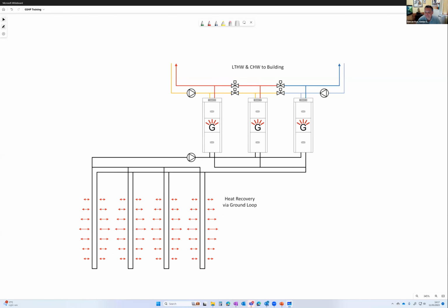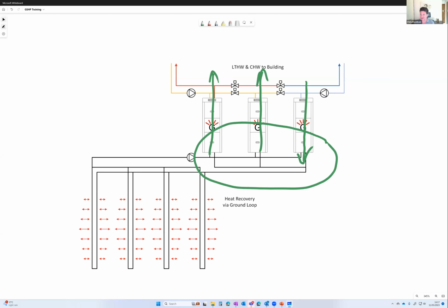Okay, let me show you what a typical commercial ground source heating and cooling system looks like. Here we've got one heat pump cooling, taking heat from the building and putting it into the loop. I've got a couple of heat pumps shown here heating, taking heat back out of that ground loop. So right away you can see energy recovery going on—instantaneous energy recovery. There are a number of different systems that allow that instantaneous energy recovery to happen.